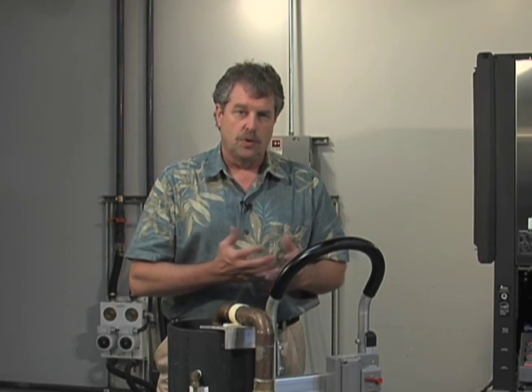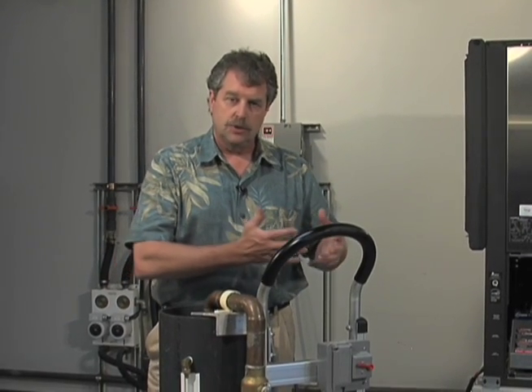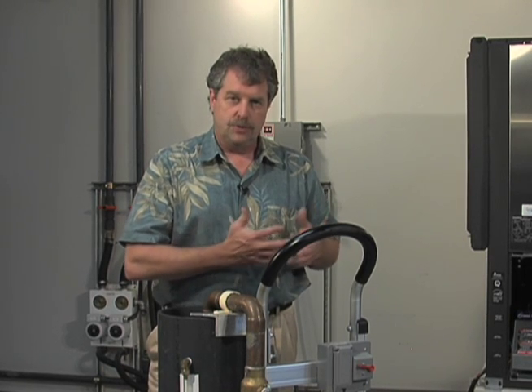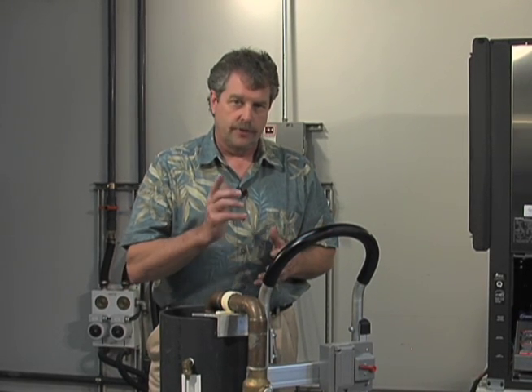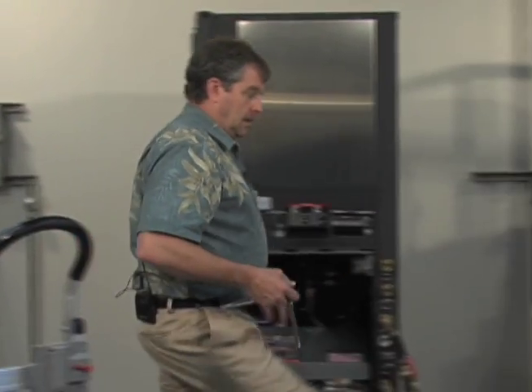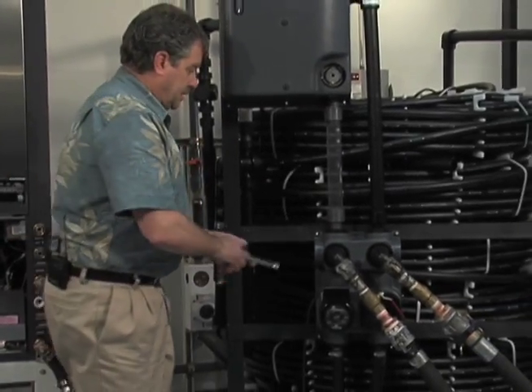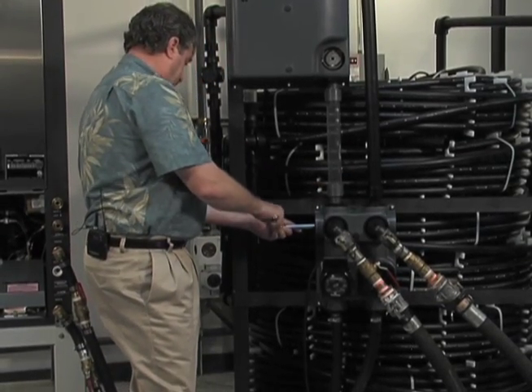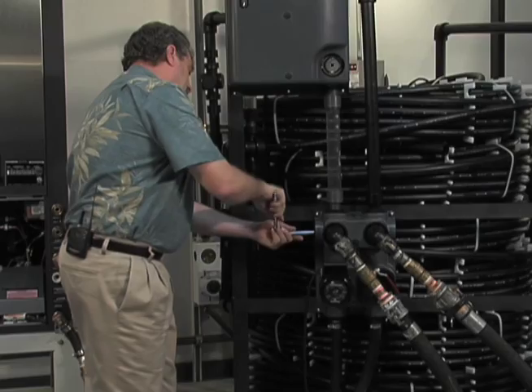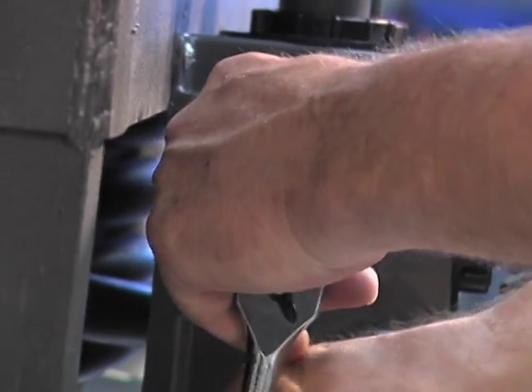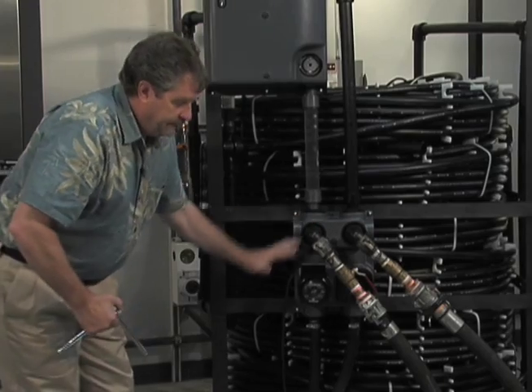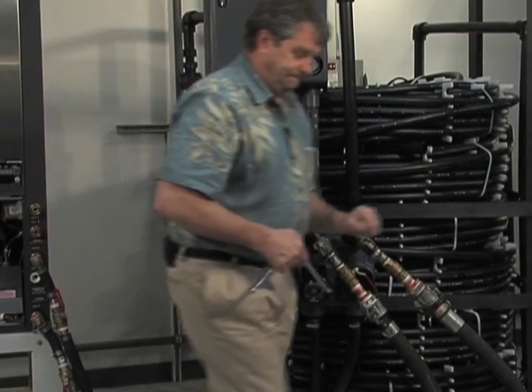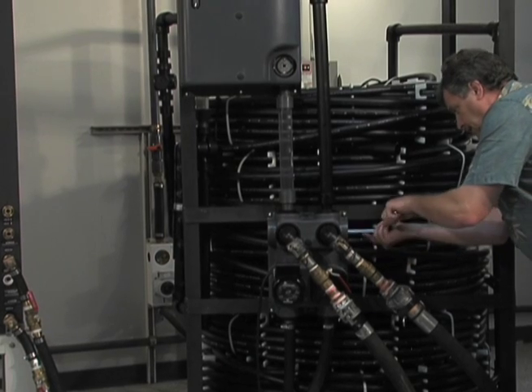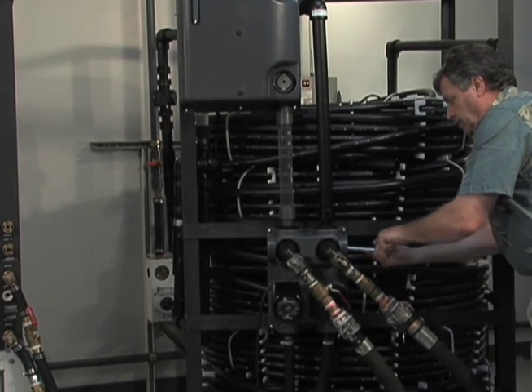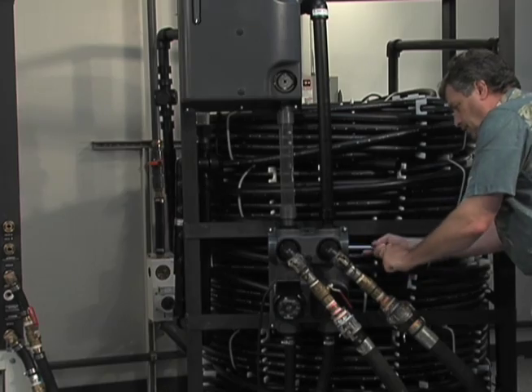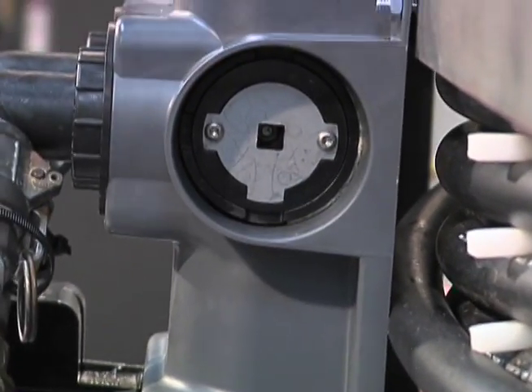So now that we have successfully moved the air out of our loop, it's time to go over to our flow controller and reorient our 3-way valves, because we still have to flush out between the flow controller and the coaxial heat exchanger, another very important step. I'm going to leave my pump running. I'm going to come over here keeping pressure on my loop. And I'm going to orient my valve so that now I'm sending all my fluid down through my coaxial heat exchanger, because I have to make sure I've removed all the air out of the piping between the flow controller and the coaxial heat exchanger inside the heat pump.